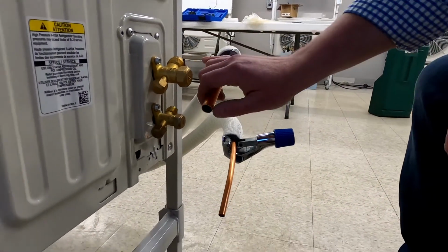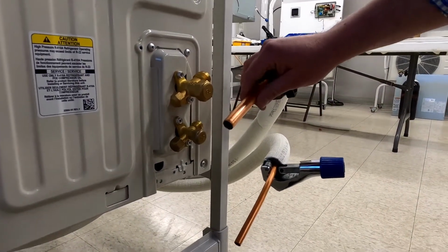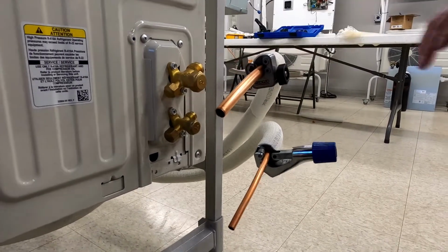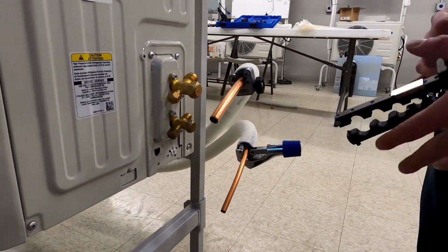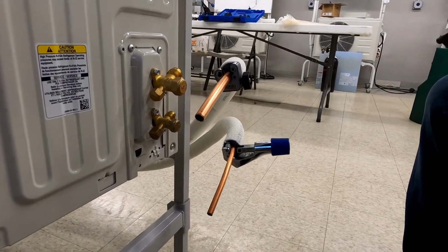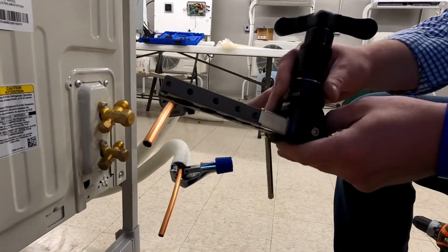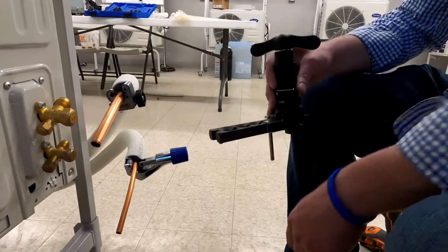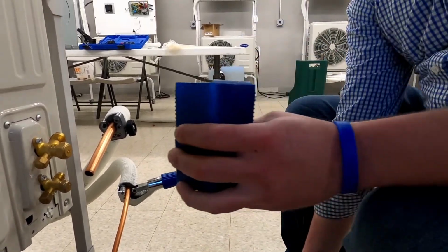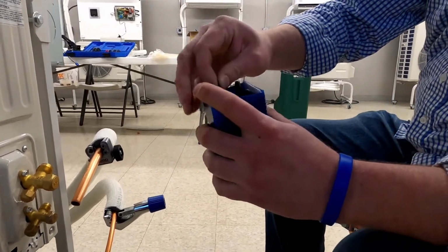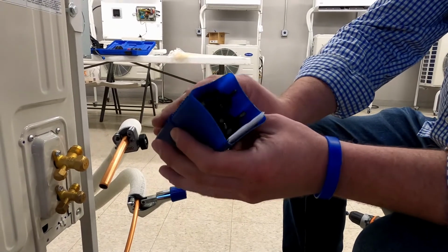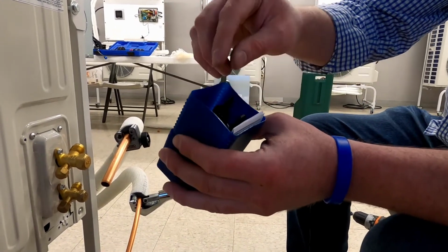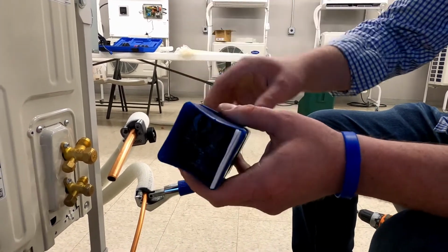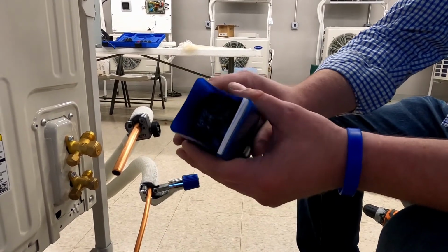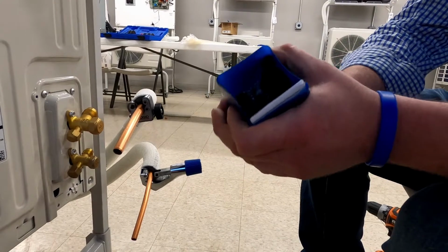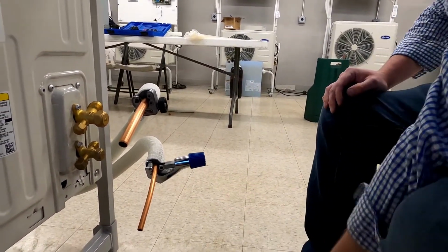After you make your cut, it's important to clean out the inside of the pipe and make sure that it's facing downwards when you do so that you don't leave any copper shavings in the pipe. Now that those steps are complete, there's multiple types of flaring tools that you can use. This one is called an orbital flaring tool, and it's one of the most common. We also have a different kind, which is much faster, and I'm a big fan of it myself, and that's the flaring spin set. One reason I like it is how fast you can make a flare. Another reason is that you can never go past the stop on it. And another reason is because it's spinning so fast, it actually cleans off the inside of the pipe if there's any burrs left over. So we're going to use both of those options today.